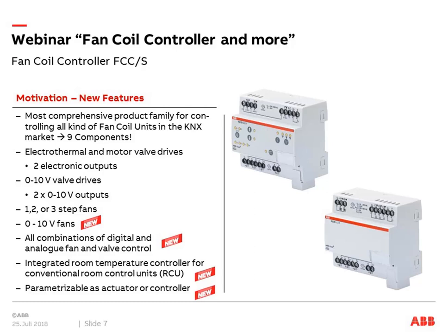For valve drive control, we can control electrothermal valve drives as before, and also motor valve drives. Motor valve drives need two contacts for open/close of the valve, so we have two electronic outputs available. You can control either two electrothermal valve drives or one motor valve drive with these two outputs. A further typical valve on the market is controlled via a 0 to 10 volt signal, also available in our new components, giving two 0-to-10 volt outputs — for example for a four-pipe system with heating and cooling valves, controllable completely with one Fan Coil Controller.